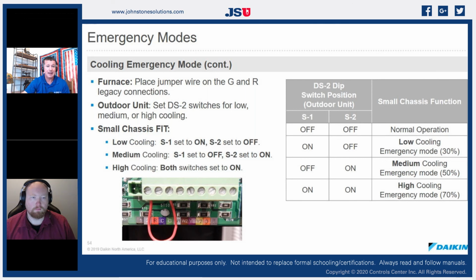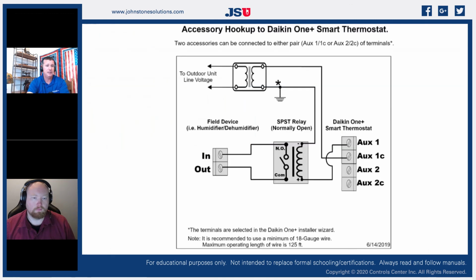All we do is go to the outdoor unit. We go to that DS2 switch and set it to whatever we want. We go to our furnace and put it in. We just jump our fan if we want to, so that the fan runs continuously. Then we go to the EEV coil and flip those dip switches and tell it as well, so that all of them know, hey, let's just run. Let's run at 30% until someone can figure out this control wire. So we have ways to get around that. We have things that we need to know.